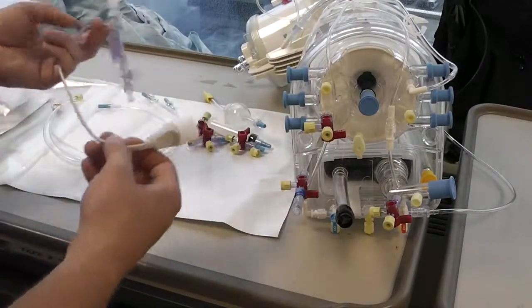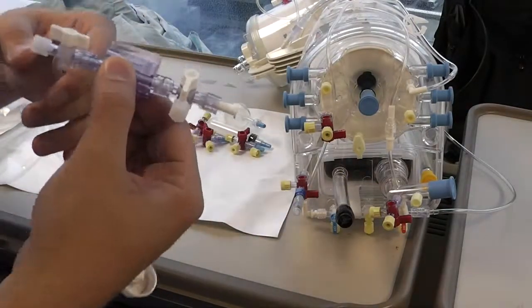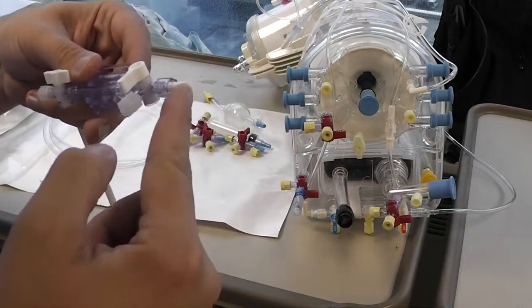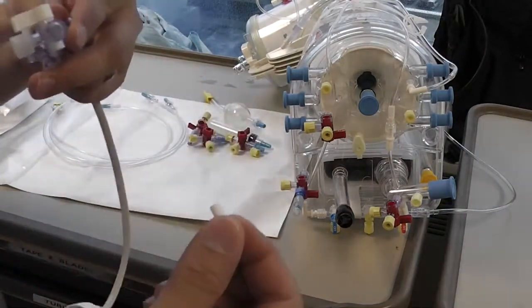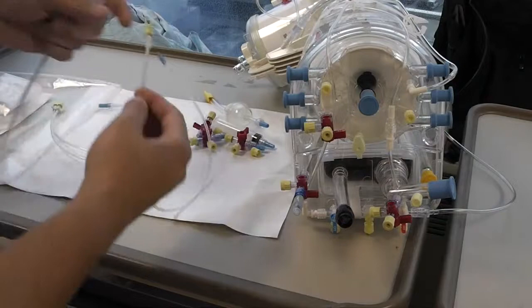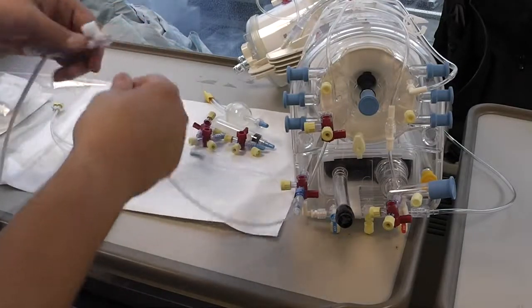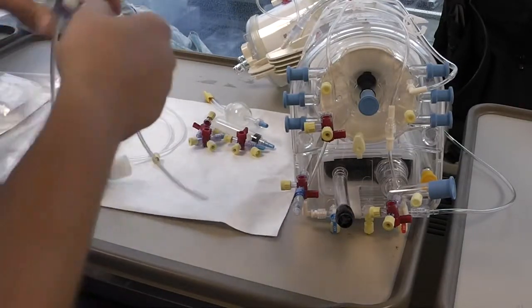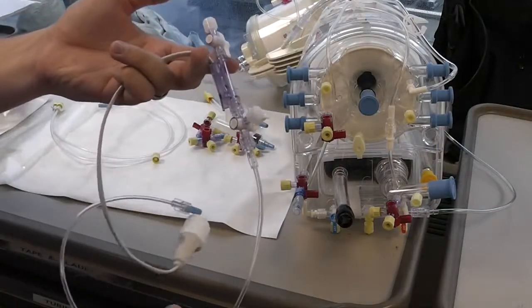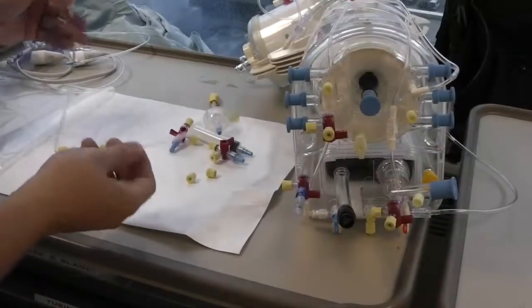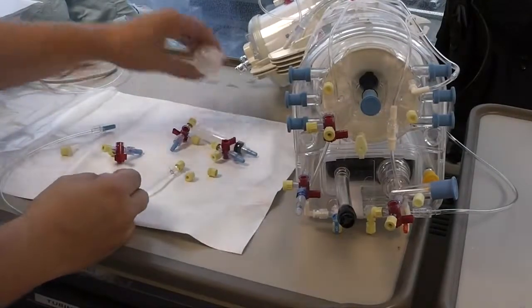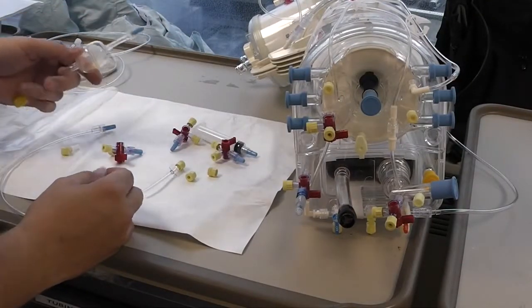You can discard everything that's in there except for the transducer itself. And we're going to remove this little white cap in the bottom there. Take off the yellow end of these lines and connect that to the transducer. We're going to do the same thing for the other. Okay, we've got one more line left, and this is going to attach to that pressure monitoring bulb.